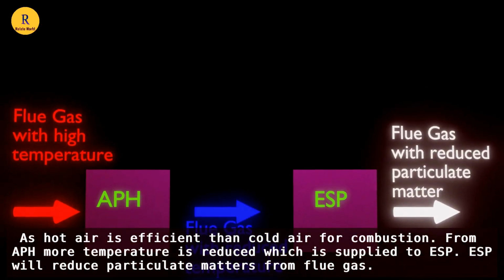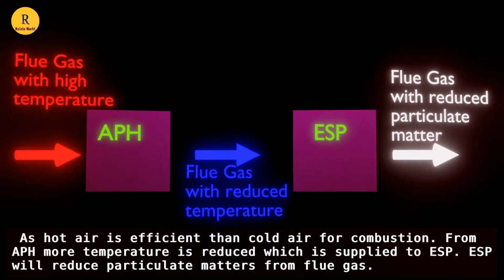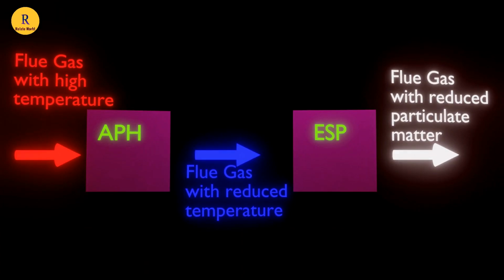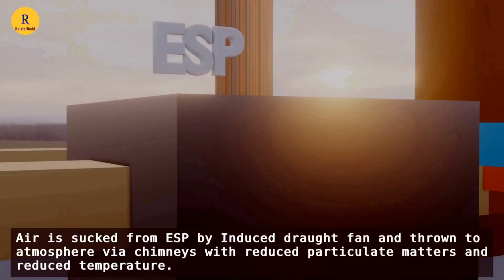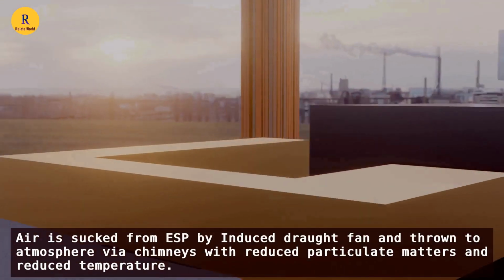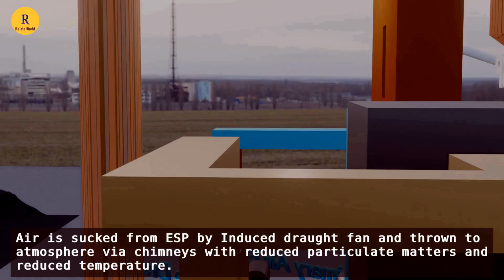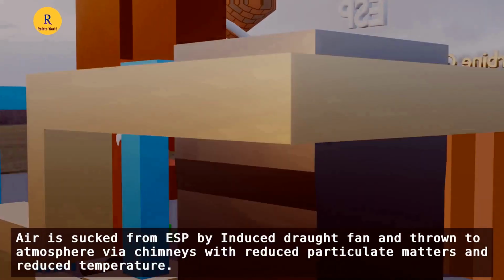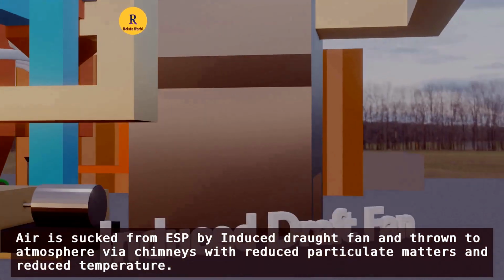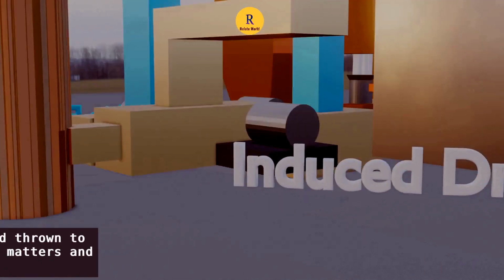From air preheater, the gas, with more temperature reduced, is supplied to electrostatic precipitator or ESP. ESP will reduce particulate matters from flue gas. Gas is sucked from ESP by induced draft fan and thrown to atmosphere by chimney with reduced particulate matters and reduced temperature.